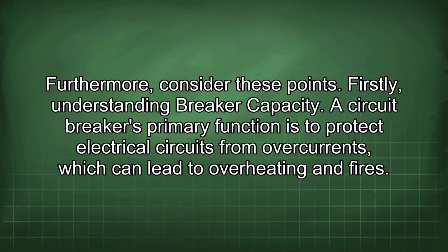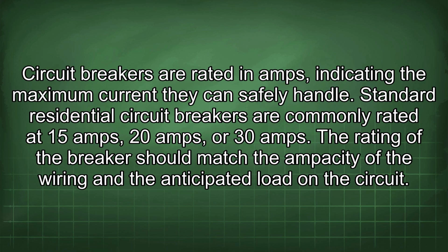Firstly, understanding breaker capacity. A circuit breaker's primary function is to protect electrical circuits from overcurrents, which can lead to overheating and fires. Circuit breakers are rated in amps, indicating the maximum current they can safely handle. Standard residential circuit breakers are commonly rated at 15 amps, 20 amps, or 30 amps. The rating of the breaker should match the ampacity of the wiring and the anticipated load on the circuit.